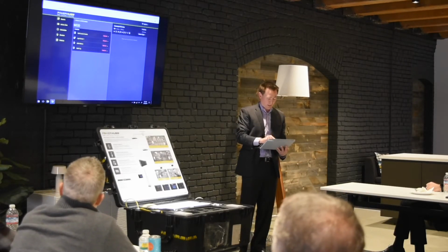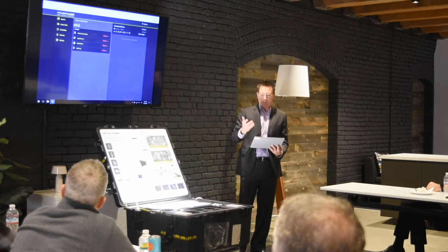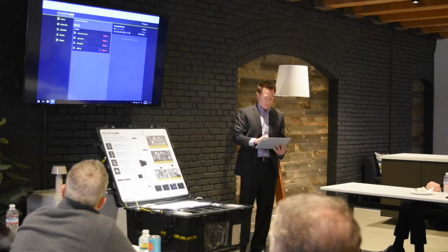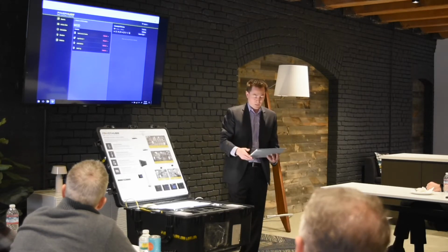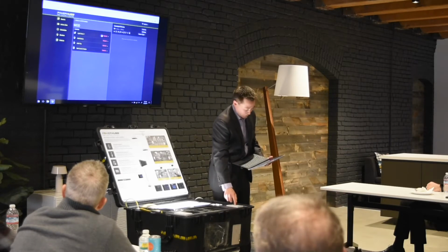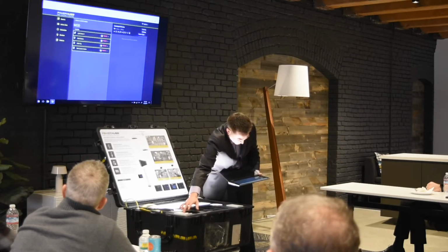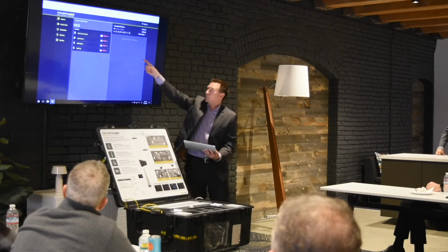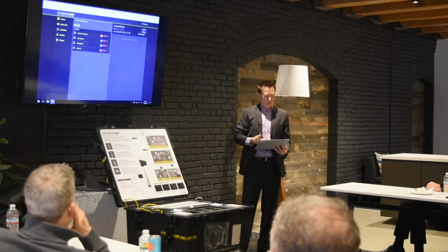If I want to see, well, what particular light is that? We have a number of ways of doing that. So this is one where I want to flash it, and now I know what light that is. If I want to see, well, which particular wall control is that, I can put that into ID mode, and now, if I hit this many times, well, it's not doing anything, so it must not be that one. If I hit this many times, then you can see that number just went sky high, and so it's the wall control I think it is. And now I can rename that. So there's a number of things that we do.